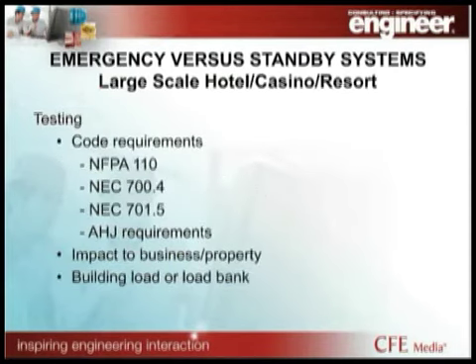So when we talk about testing, Gerald referenced NFPA 110 and testing under load. One of the other reasons that on large-scale systems we're very big proponents of closed transition paralleling, meaning make before break. Obviously, if you have an outage, the system is out, but when the utility is restored, you can go closed transition back from generator. That eliminates one disruption. For testing purposes, if you're in closed transition mode, you can actually test the system under load and run through all the transfers they need to go through without disrupting the facility. In our experience, the larger systems that are open transition inevitably don't test. Or if they test, they just start the generators, which is probably just as bad as not testing.